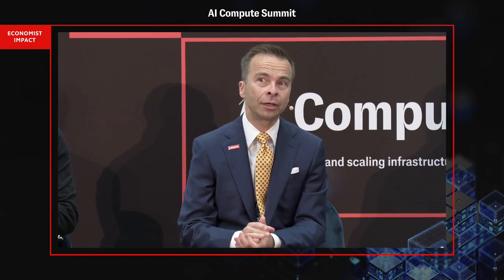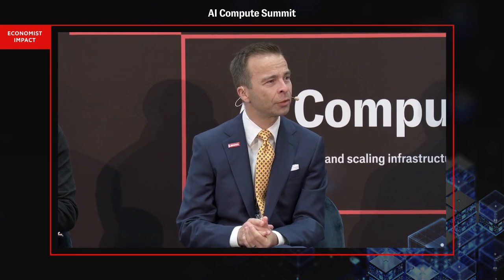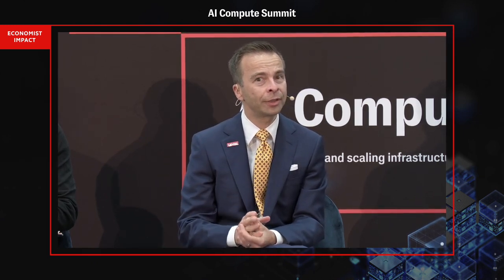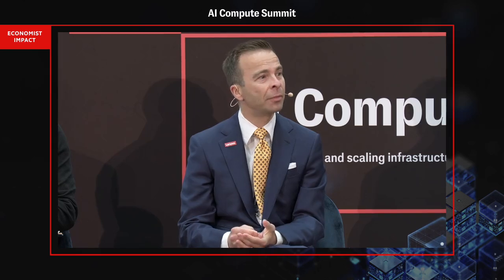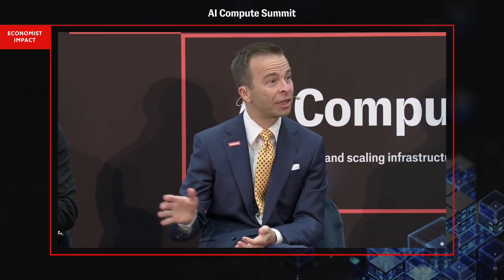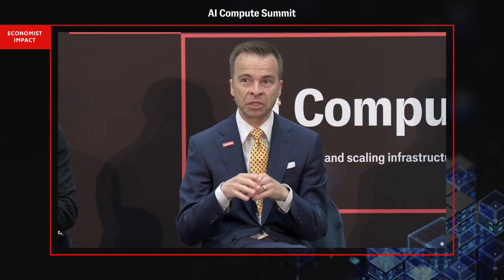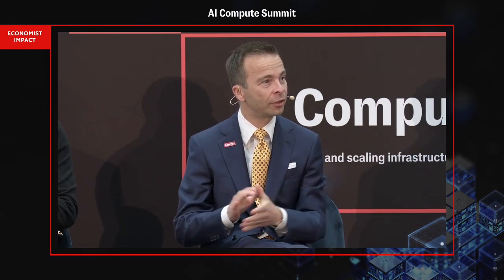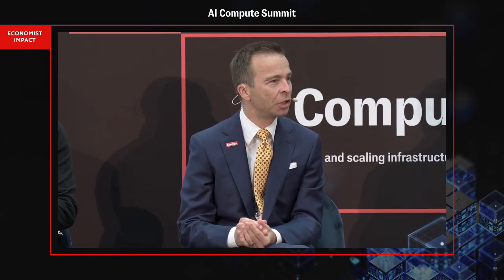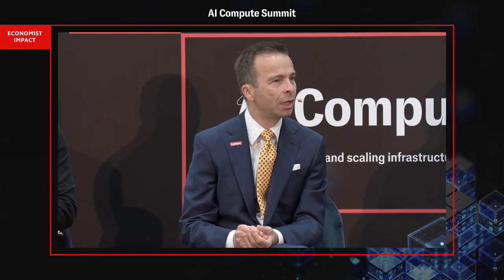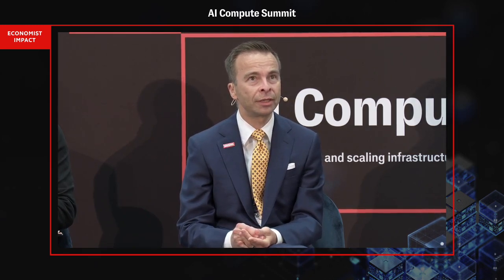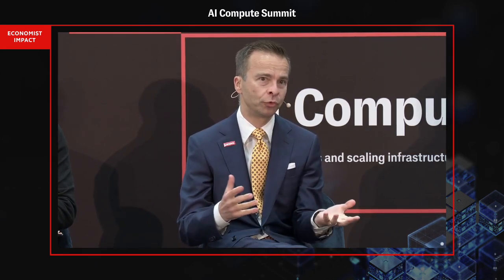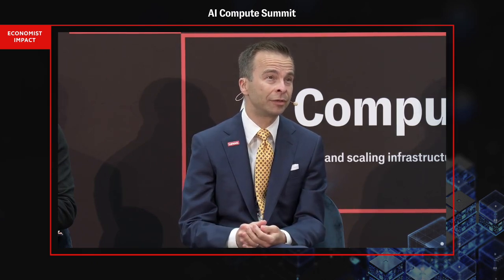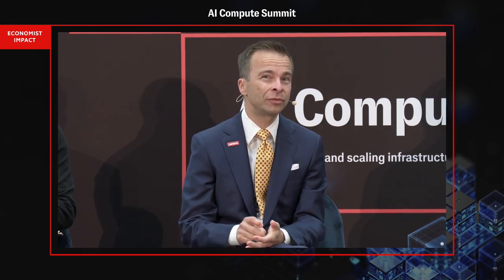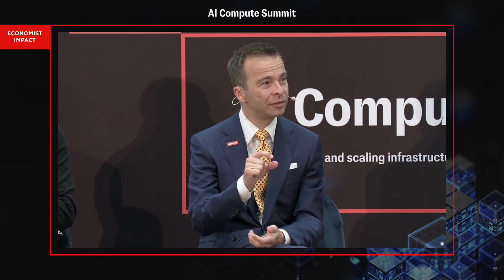I would dissect this, in my view, that immersion has some challenge in how you'd service a system, since you'd have to drain it and so on. But if you have an application case where that doesn't matter, because you're just putting it there once and never touching it again, a large-scale, very homogeneous system staying the same forever, that's probably a technology that's viable. If you look at more sophisticated, higher-demanding environments where you need more serviceability and higher reliability, and also need to cope with higher densities and heat dissipation, like GPUs getting denser and hotter at the same time...